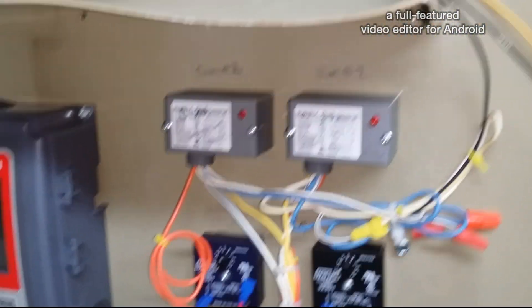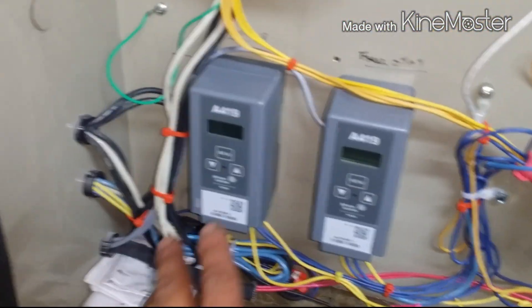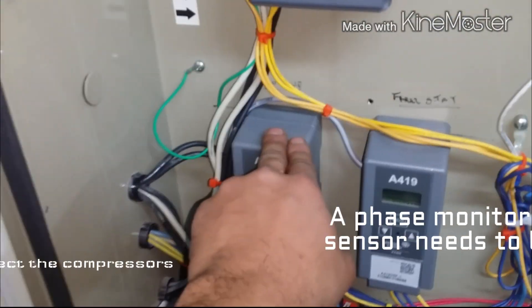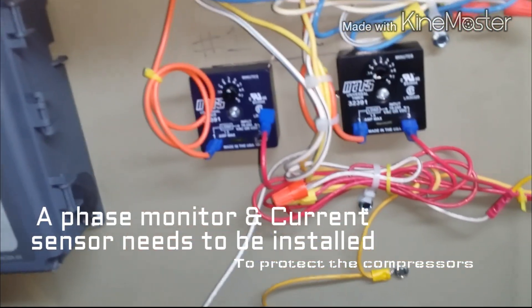Trane wanted roughly sixteen thousand dollars to replace the boards, so we kind of just redesigned the control panel a little bit. We got a freeze stat — this is another stat that basically it's just a pump down system that controls the solenoid, goes to the differential switches and the flow switch, a couple other safeties involving water.